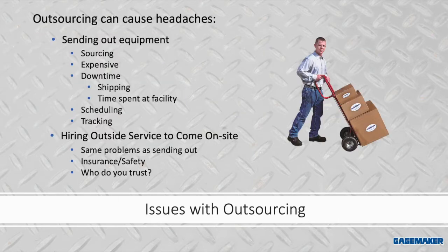If you're calibrating by sending to an outside source, there are some headaches involved. You have to send out the equipment, so there's time spent outside your facility where you can't use that instrument. You're basically at the mercy of the outside service. There's the added expense of paying someone to do this, and sourcing a service you'd actually trust. Alternately, if you had an outside service come on site, there's scheduling, downtime, accommodating them at your facility, insurance and safety liabilities, and ultimately, who do you trust?